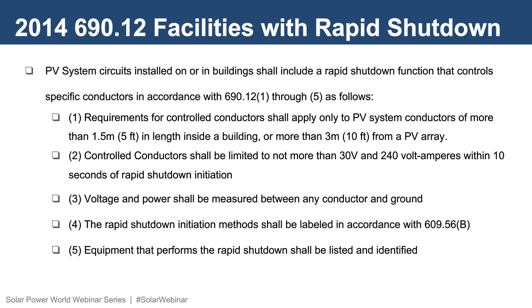The controlled conductors shall be limited to 30 volts and 240 volt-amperes within 10 seconds of rapid shutdown initiation. However, a tentative interim amendment, TIA, has been issued regarding this requirement of rapid shutdown, which states that the initiation must happen within 30 seconds, the same as in 2017. The 2014 rapid shutdown labeling requirement is quite simple. A label must be installed stating: photovoltaic system equipped with rapid shutdown.